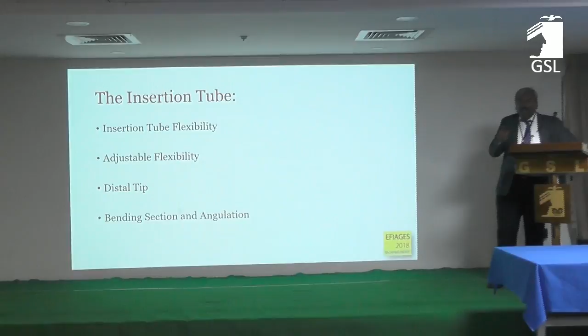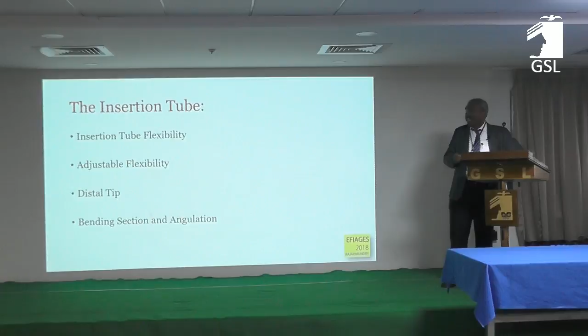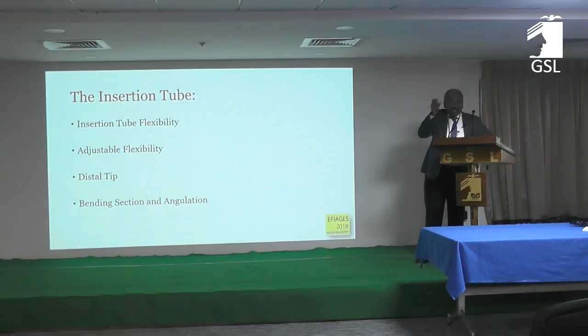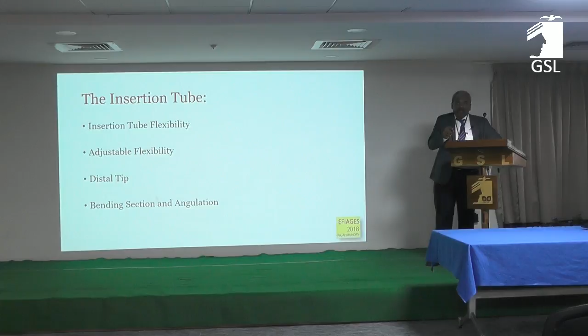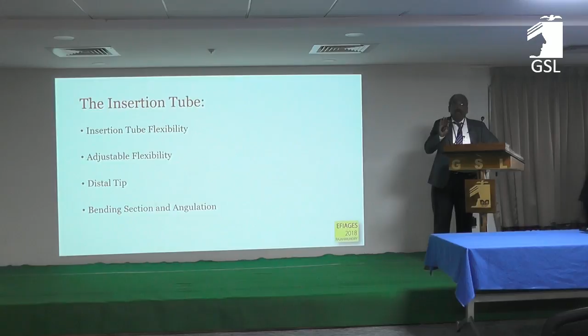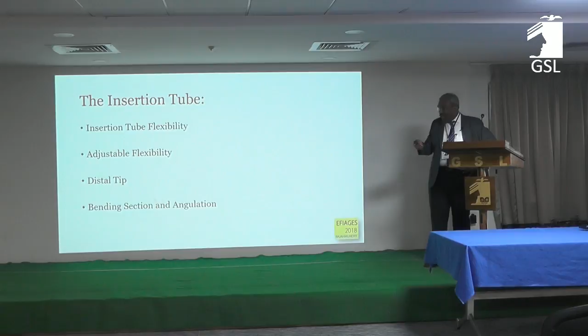So the insertion tube which we have spoken about, the flexibility of the tube is the most important thing. It should not be so flexible that it buckles, and it should not be so rigid that the patient finds it difficult to take in. That is why in colonoscopy I showed a knob to adjust the stiffness, and then the safety of the distal tip. It should not hurt the patient, at the same time it should be steerable, and give the best possible image and comfort for the endoscopic operator. Of course, the bending section and the angulation, which I will touch upon now. What goes into this black tube?